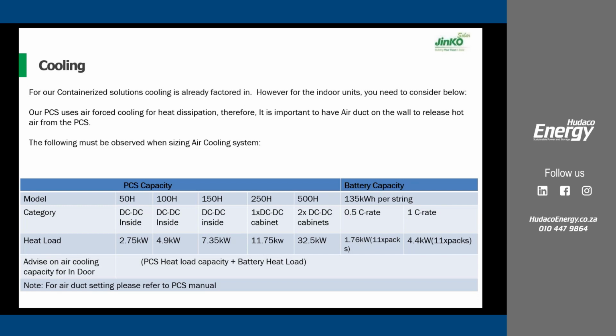But for the indoor units, I think it also needs to be site specific. That is, you need to assess the site, the power room where you're going to have the batteries, and be able to calculate the heat load. But we've given a guideline on the heat load capacity for the PCS. For the 50 kilowatts, you're looking at around 2.75, 100 kilowatts around 4.9, all the way to 500 kilowatts around 32.5. Then for the batteries, with a standard C rate of 0.5, we're looking at around 1.76 for one cluster of batteries. So if you're looking at around 10 clusters, that means 1.76 by 10, which makes it 17.6 kilowatts.